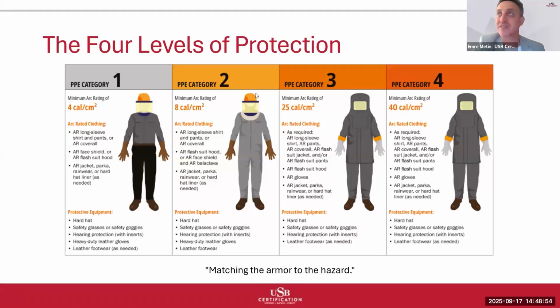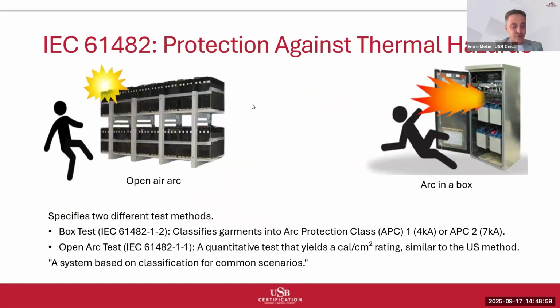I'm increasing the speed of the presentation a little bit. The European approach. Now let's examine the IEC approach, which takes a somewhat different path to achieve similar protection goals. The classification of the arc rating has two boxes, and also two test methodologies. One is arc protection class 1, which passes at 4 kiloampere test current. The other one, arc protection class 2, APC2, passes at 7 kiloampere test current.